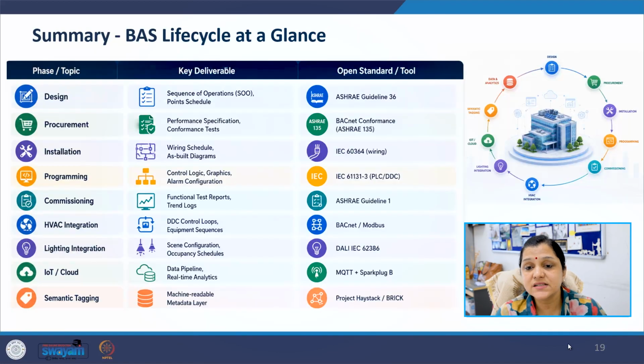So, summarizing this discussion, we look at the building automation life cycle at a glance. This table summarizes the entire building automation life cycle. Each phase generates specific deliverables. For example, the design phase creates the sequence of operations and point schedules. The procurement phase focuses on performance specification and conformance testing. The installation phase produces wiring schedules and as-built diagrams.